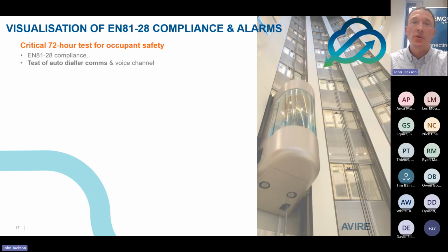In terms of the EN81-28 alarm, the critical occupant safety test here is the 72-hour test. Someone asked me recently, why is it 72 hours? I asked a colleague, and it's apparently because that's the length of time somebody can stay alive for in a lift if they get trapped. 72 hours was the chosen amount to alarm out and check that the auto dialer could work.